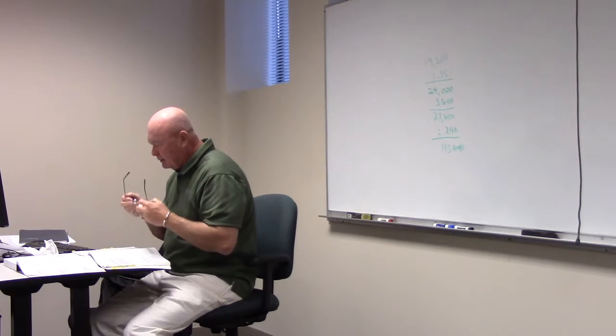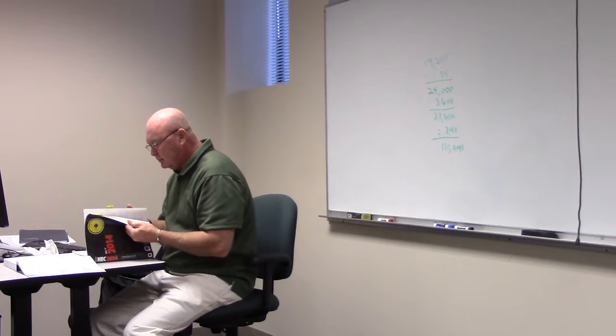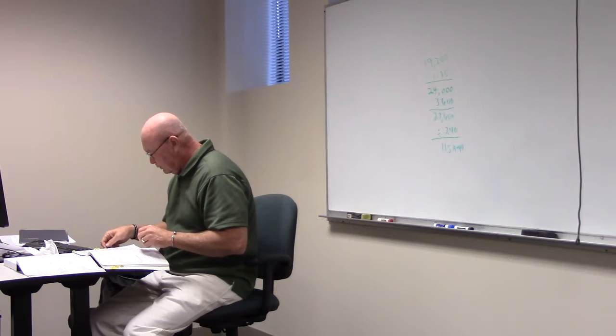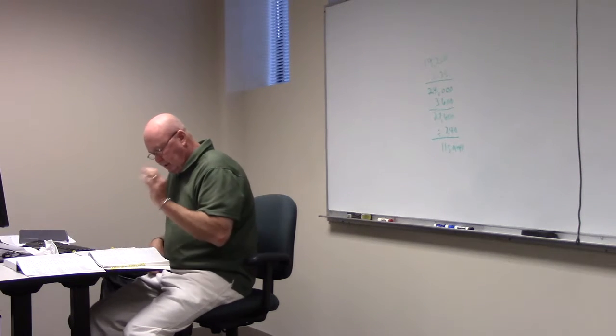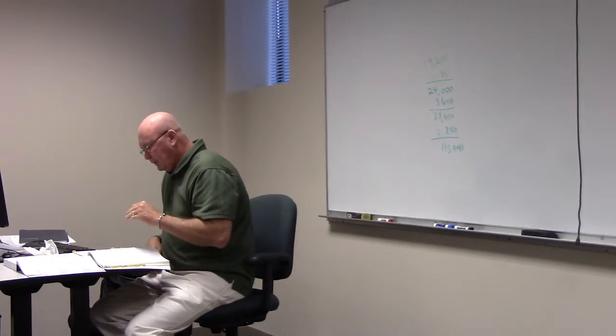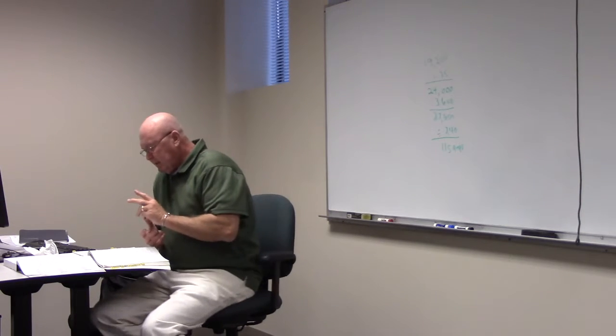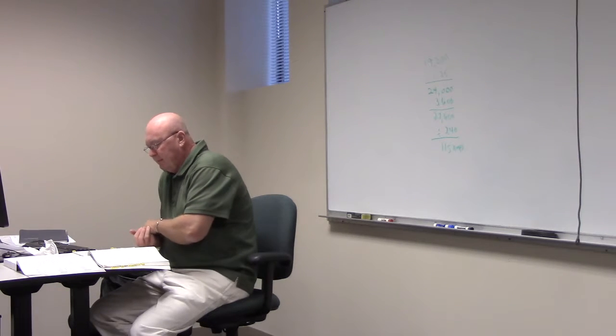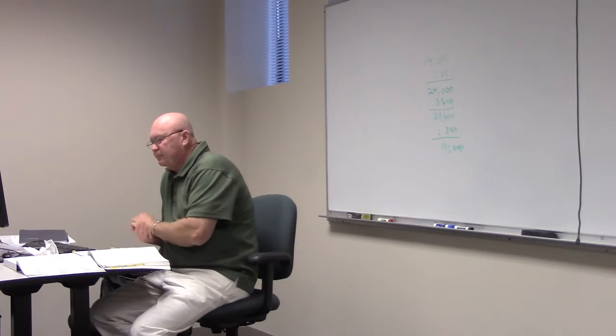But now let's do one thing. Let's not stop there. Let's go to 240.6 and just look at something. 240.6. And we see that common standard ratings for overcurrent devices are fuses. And so we've got 115. What would be the standard size fuse or circuit breaker that we'd have to use for this circuit? Wouldn't that be... 240.6. 240?